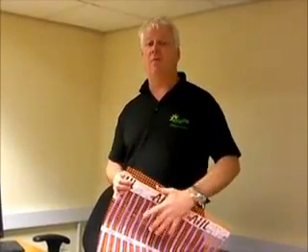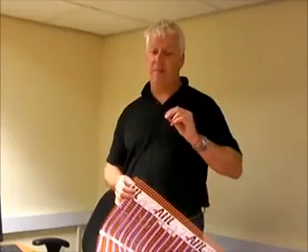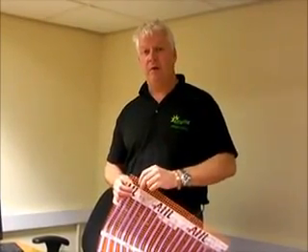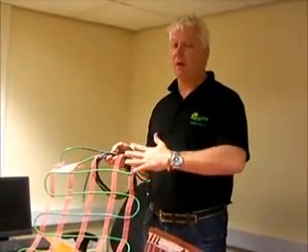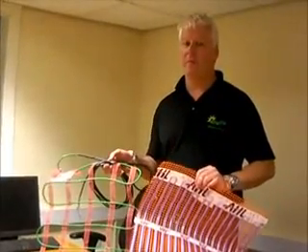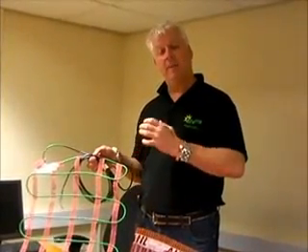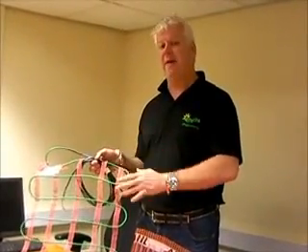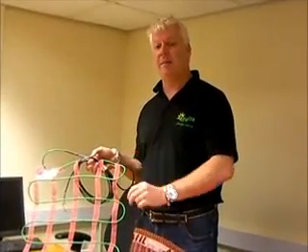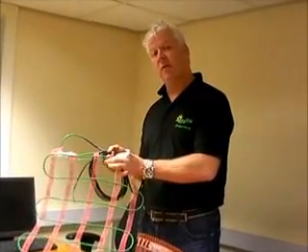Its heating uptime is three minutes from cold, and because you get more of it, it heats the room quicker and goes off — as we've demonstrated with 46 passive houses, it's about response time and coverage. With a cable system or water system, the working temperature has to be very high because there's not enough of it; it needs to disperse temperature between large gaps and therefore operates at a high temperature. This ribbon system doesn't go above 30°C, which means it can go directly under any flooring product.